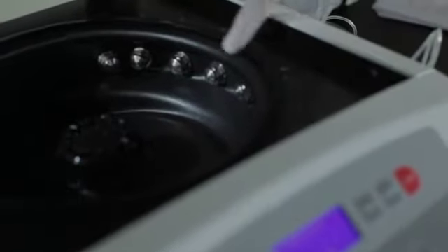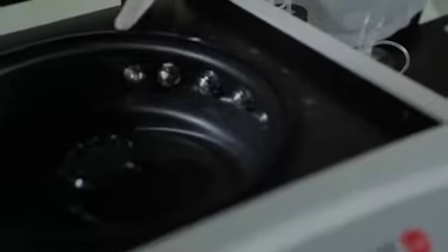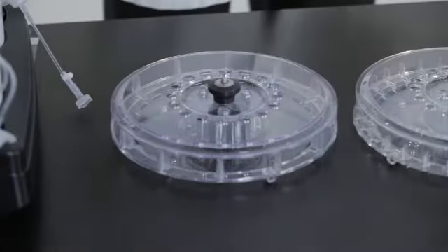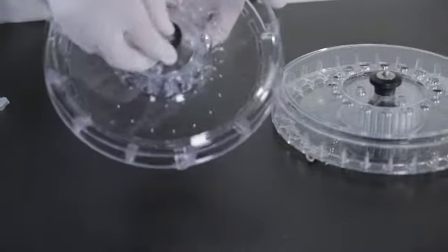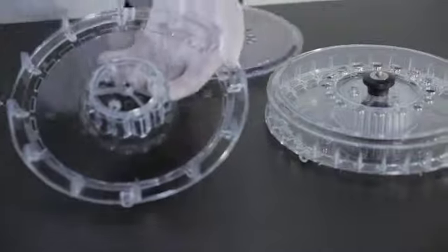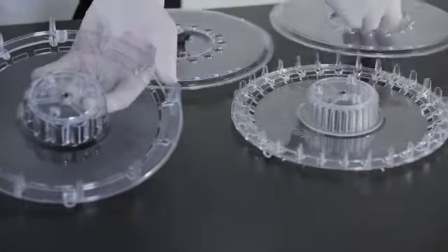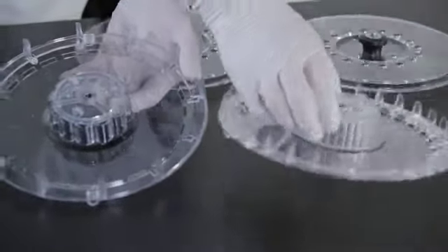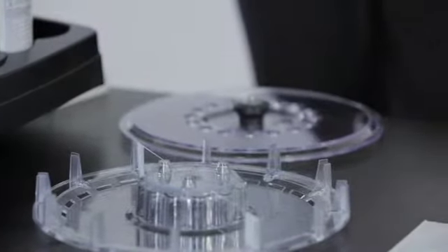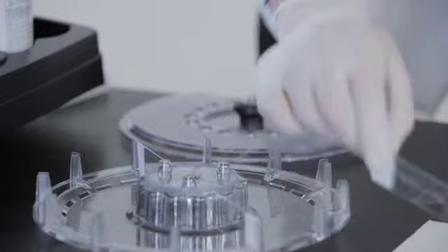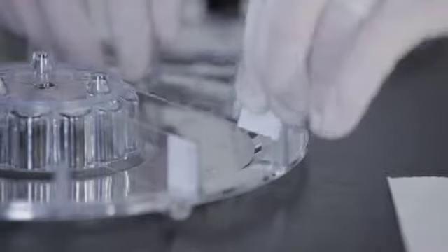The stainer has 5 reagents and 6 nozzles. The D reagent is deionized or distilled water and is sprayed from 2 of the 6 nozzles. The TB stainer uses either a 12-slide carousel or a 30-slide carousel. The stainer automatically recognizes the size of the carousel, so no programming is needed. The 12-slide carousel should be loaded with the label of the slide towards the outside of the carousel.